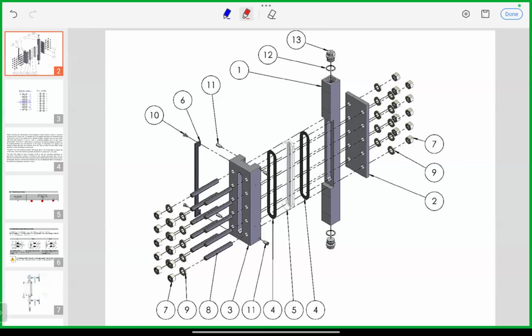If you don't allow it to come to the same temperature and tighten with torque, when it expands the actual torque becomes very high. So the procedure is: after overhauling any gauge glass, assemble and tighten with only finger tightening, no torque tightening. Then assemble on the boiler, let it reach the same temperature, and then tighten in multiple steps with final torque tightening.